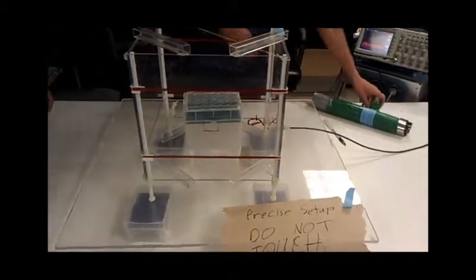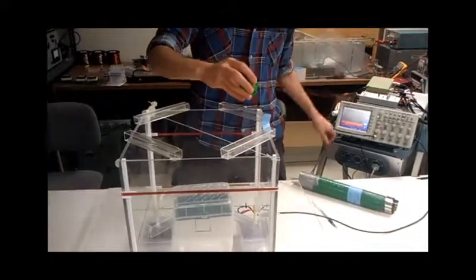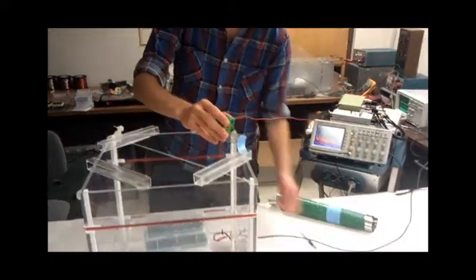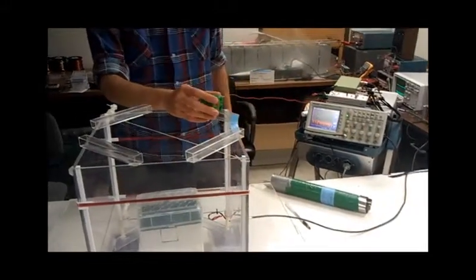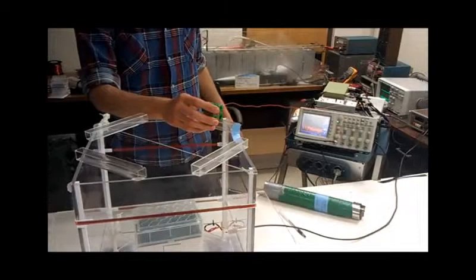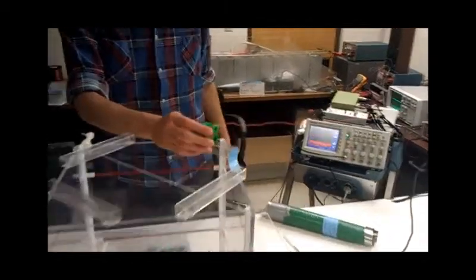And then you just put the probe directly in the center, which my cable's not long enough right now, and you turn on a field, or you turn on a current, create a field. You know what field you're creating. You can measure it on the oscilloscope and calibrate it that way.